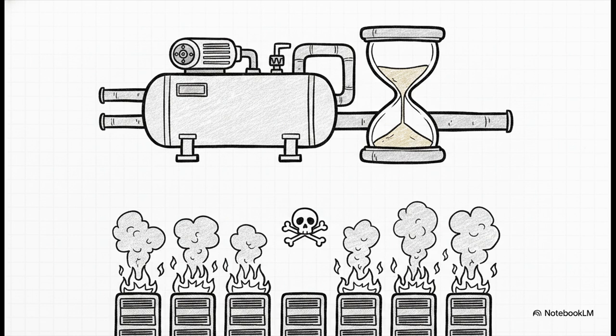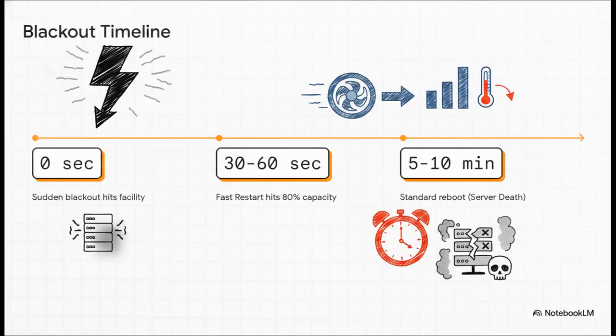Standard industrial compressors have built-in safety protocols. They need to slowly balance their internal pressures before they'll even allow themselves to turn back on, a process that takes 5 to 10 agonizing minutes. In a modern AI data center packed with high-density chips, 10 minutes without cooling literally means the servers fry themselves. Total server death by overheating. Just look at the timeline to really understand the stakes here. At 0 seconds, blackout. We know waiting 5 to 10 minutes equals server deaths.